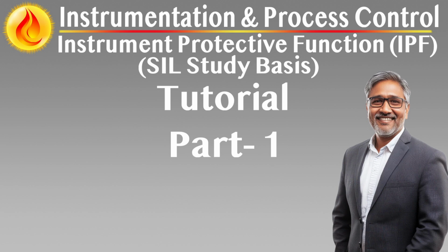For example, SIL-1 functions address lower consequence hazards or those with additional layers of protection. SIL-2 and SIL-3 functions protect against higher consequence events with fewer tolerances for failure. SIL-4, while theoretically defined, is rarely used in industrial process applications due to its extreme design and cost implications. The SIL assignment is typically derived from layers of protection analysis, LOPA, or similar semi-quantitative methods, with each IPF evaluated for independence, reliability, and effectiveness.